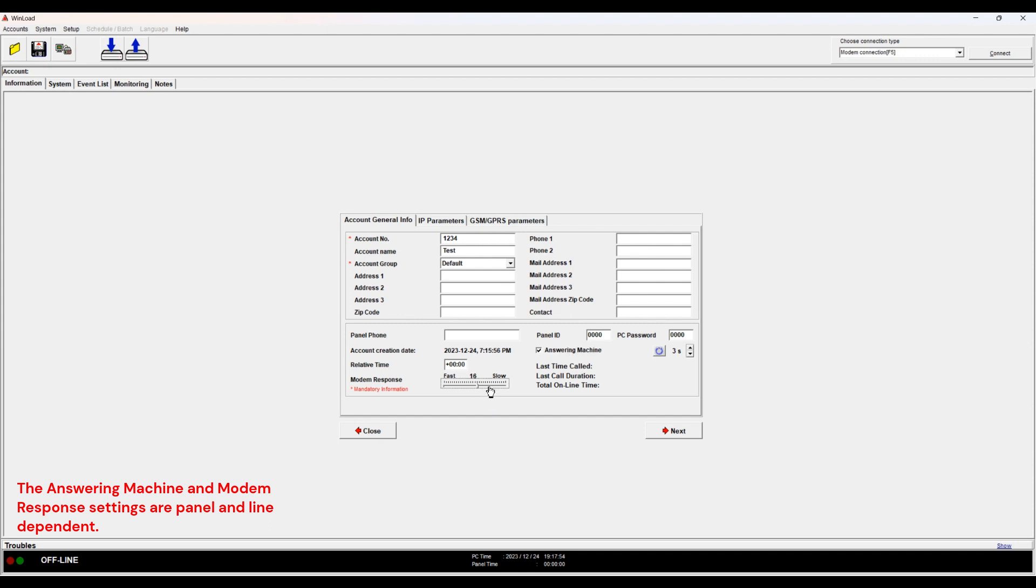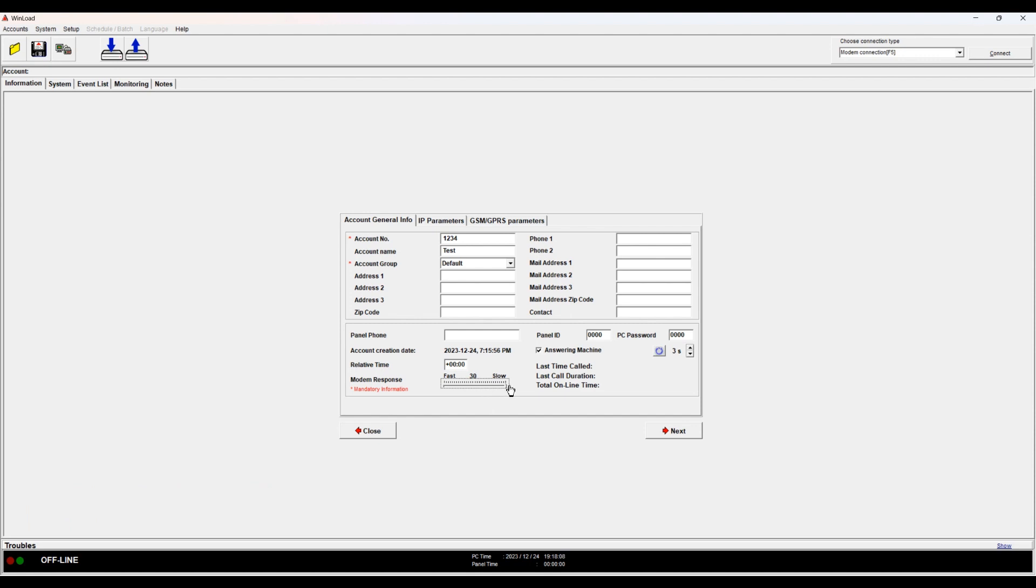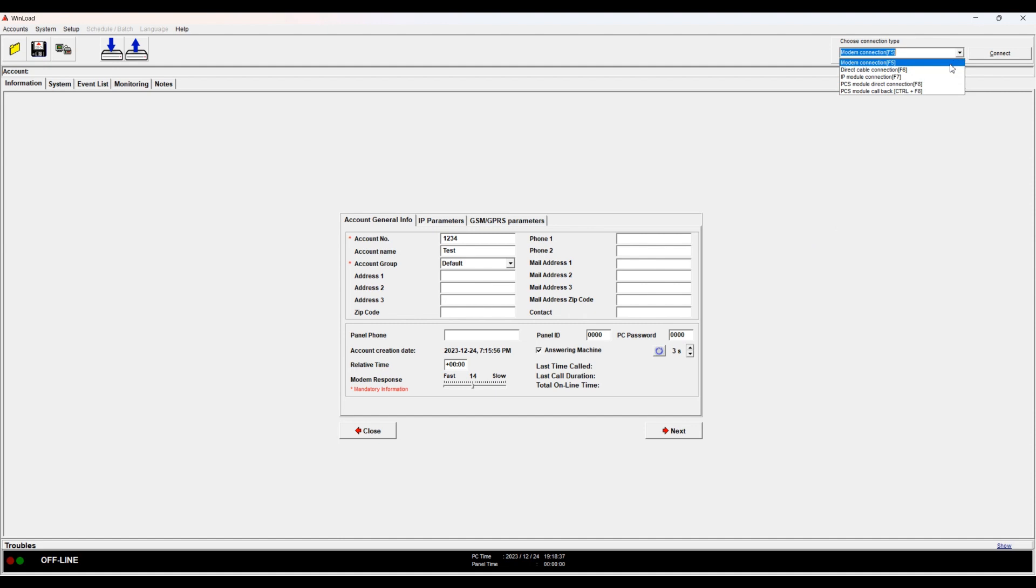You will have to experiment with this, unfortunately. With phone line it's a little bit tricky. I noticed with newer panels you sometimes have to put it all the way down or experiment with these settings and keep track and keep trying until it answers. Surprisingly, with older panels like the 1738, I have to set it to a faster modem response so I can log in. In my case here, I'm not dialing through a phone line, so I'm dialing with the direct cable. I'm going to select here, I can press F6 or set direct cable connection and then click Connect.